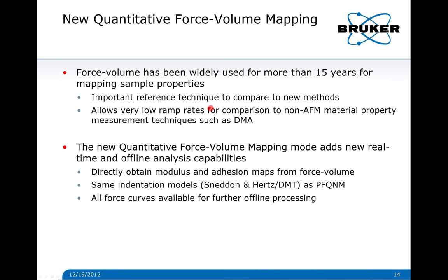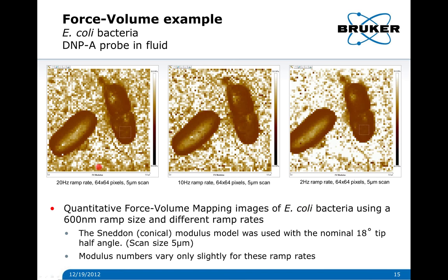Let's talk about the new quantitative force volume technique. This is the real-time force volume just like what we've done for 15 years. Basically it's a reference technique to allow comparison with QNM, and it also allows very low ramp rates — down to less than one hertz — for comparison to non-AFM material property measurement techniques such as DMA. We have new real-time and offline analysis capabilities to give us modulus and adhesion maps from force volume, using exactly the same models as peak force QNM so you can more easily do these comparisons.